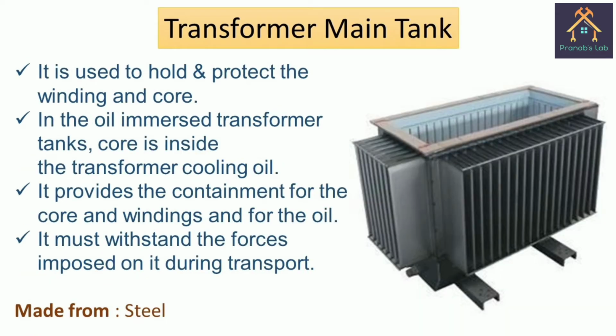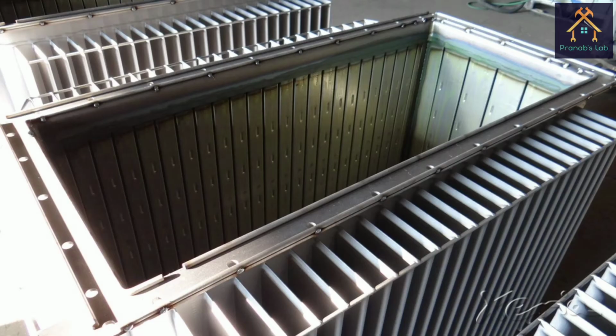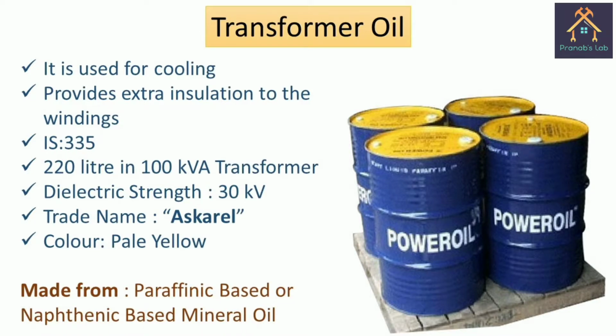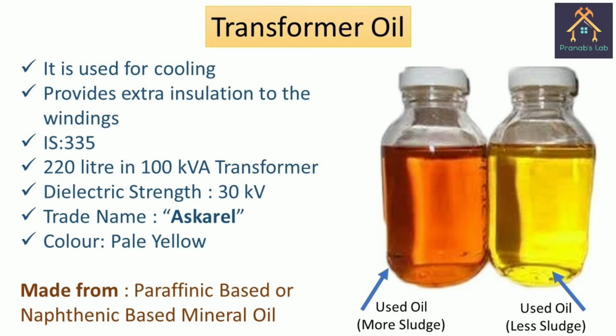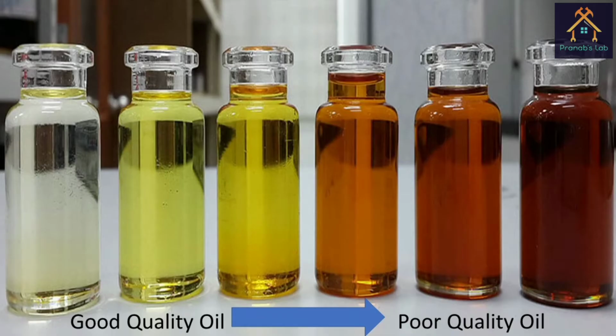The transformer core with windings is inserted inside the transformer main tank. It acts as the container for the core and windings and is completely filled with transformer oil. The transformer oil plays a vital role in this type of transformer. Actually, the transformer oil is a paraffin based mineral oil used for cooling and providing extra insulation for the windings. Depending on time and continuous use of the transformer, the quality of the oil gets lowered, and after a certain period of time it should be replaced.